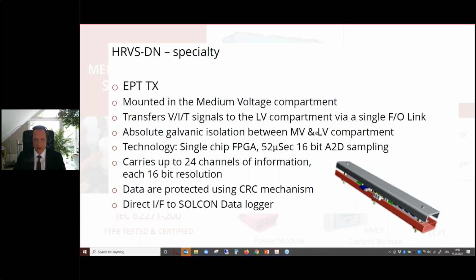Okay, you could say a CT or a VT itself is a galvanic connection, but it can give you an uncomfortable feeling if you have a wire going from the medium voltage to the low voltage compartment. And with this device, this is completely excluded. Also, it is connected by fiber optics to the data logger.